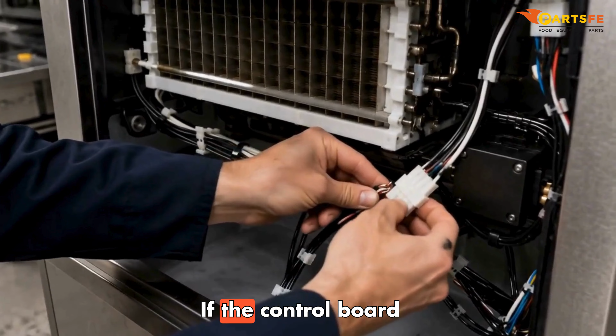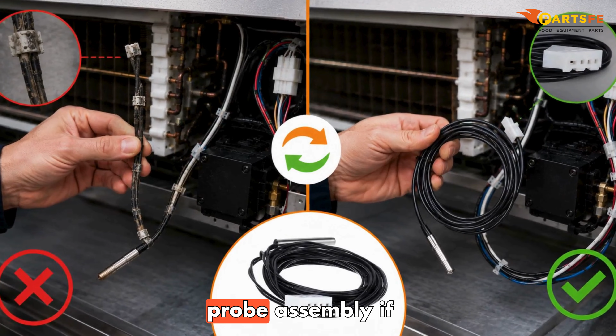If the control board is receiving incorrect or unstable temperature readings despite secure connections, the probe assembly may have failed internally. After completing all diagnostic checks, replace the dual temperature probe assembly if it no longer meets the required specifications.